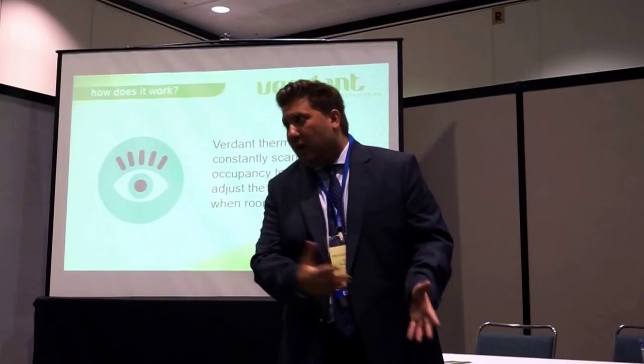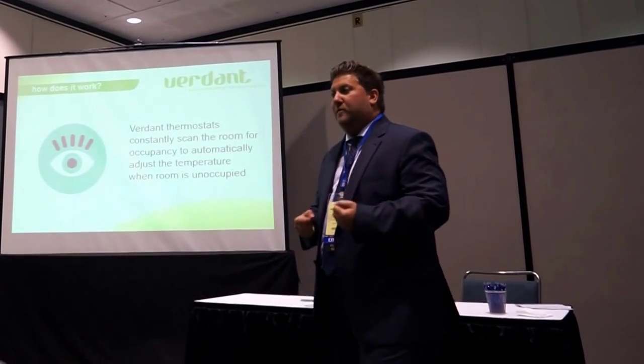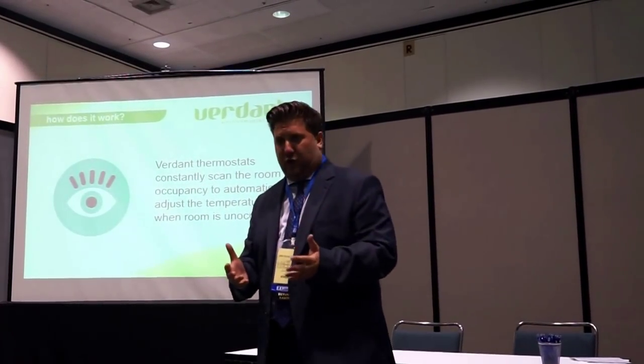Except when guests leave, the room keeps running at whatever they set. My hotel room right now is still pumping 67 degrees of air conditioning while I'm gone — that's a tremendous amount of waste. I'll be gone about eight hours today, and based on my expertise I estimate they'll throw about 60 cents in the garbage because they're pumping air conditioning into an empty room. If they had an occupancy sensor that knew the room was empty and could set back temperature to a reasonable level, I'd be fine walking back into a room that was only a few degrees warmer, and the hotel would save significantly on electricity at year's end. Occupancy detection is the key to an effective energy management system for guest room HVAC.